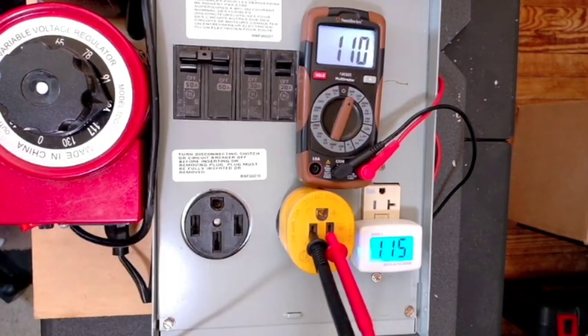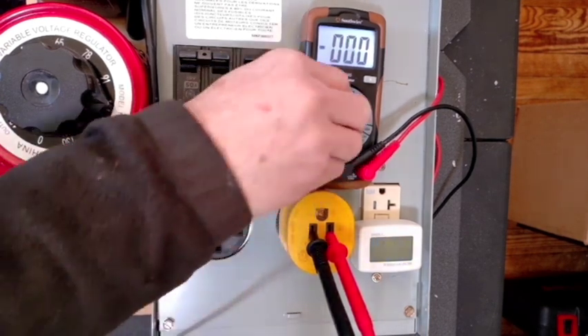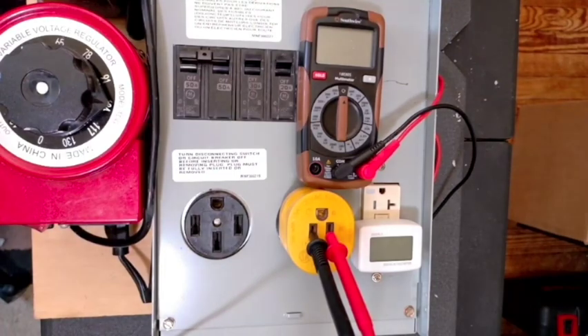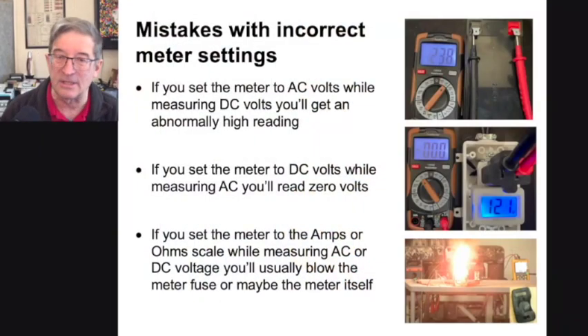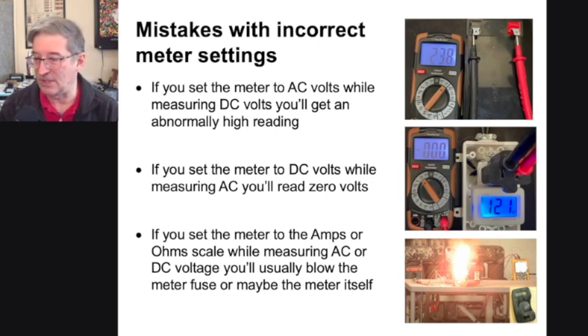It says it thinks it's 0 volts, but it isn't—it's actually 110 volts. What that can do is really, really dangerous, because what can happen is you set your meter accidentally into DC, plug it into an AC circuit, it looks like 0 volts, you stick your screwdriver in there, and you get shocked or really, really hurt.